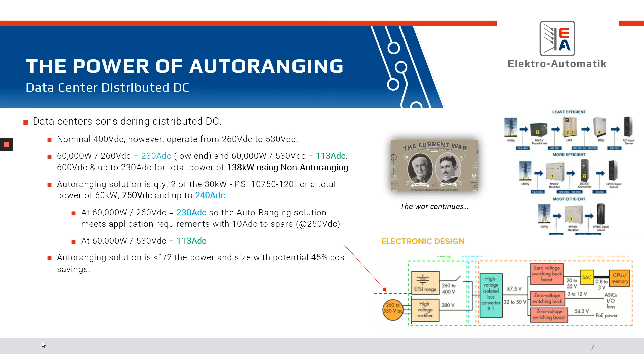Let's look at data centers — the war continues between AC and DC. What's going on right now is that the current method of providing power to servers is considered the least efficient. Data centers consume an enormous amount of power, so increasing efficiencies can result in significant cost savings. One approach being looked at is: instead of bringing utilities through a medium-voltage transformer, UPS, power distribution unit, and then AC into the server rack — and doing the AC-to-DC conversion at the rack level — the most efficient way would be to rectify right from the utility line and feed high-voltage DC throughout.